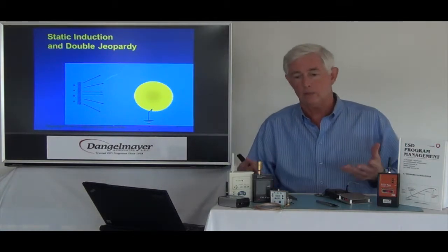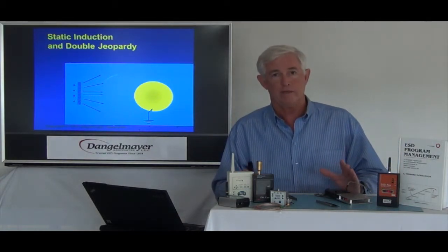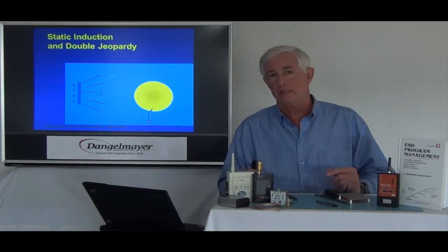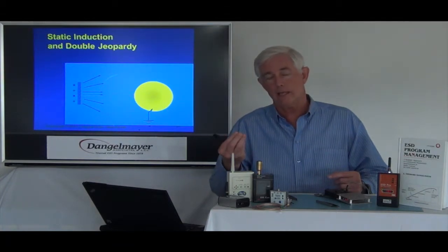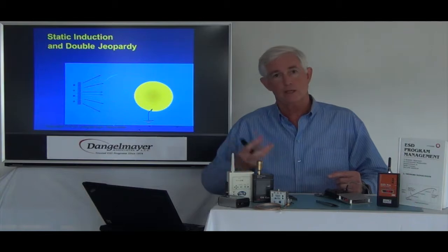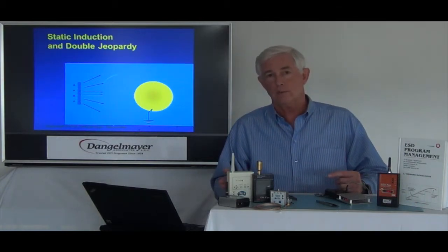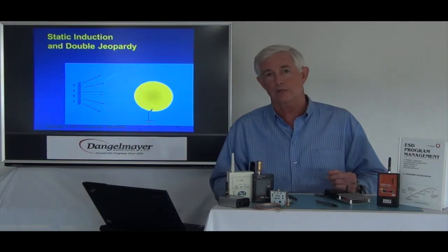Now, what is this all about? Well, it's a confusing topic, and we see double jeopardy happening within the factory in a variety of ways. We've seen it, as an example, in automated test handlers, where there are plastic elements within the handler, devices coming through, getting charged once, discharged, and then discharged again. So it's a real phenomenon that does occur, and again, gives you two stresses for the same source of charging. Very important scenario to fully understand so that you can implement it effectively in the factory.